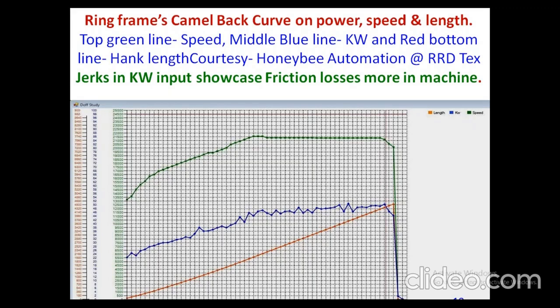Here, after conducting the energy audit, we are going through all the parameters. This textile mill has an RRD, and Honeybee Automation has done the ENMS. We can see that when there is a step change and an increase in the spindle speed, there is a jerk in the kilowatt. Here we suggested that they replace all their tin roller bearings with the specialty grease, to try to reduce the friction between the components from the main motor to the spindle. Automatically this becomes straight lined and smoothened, and the energy savings is achieved in this mill. After that, we started suggesting it to each and every mill wherever possible. I will just go in depth on this one also.